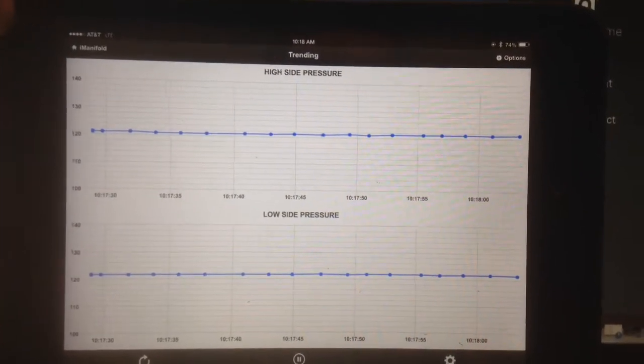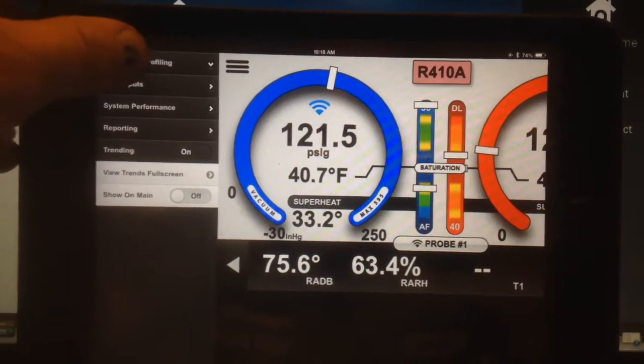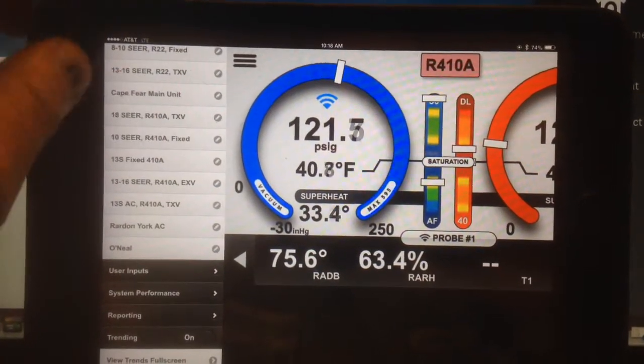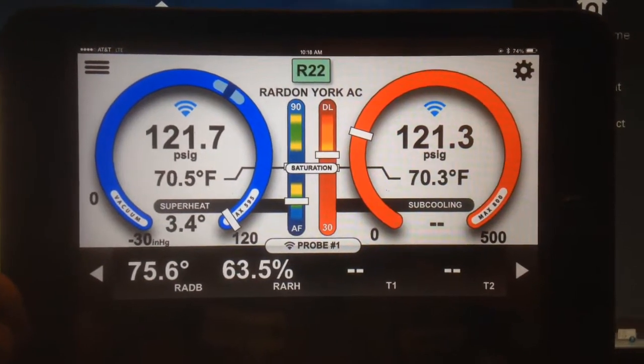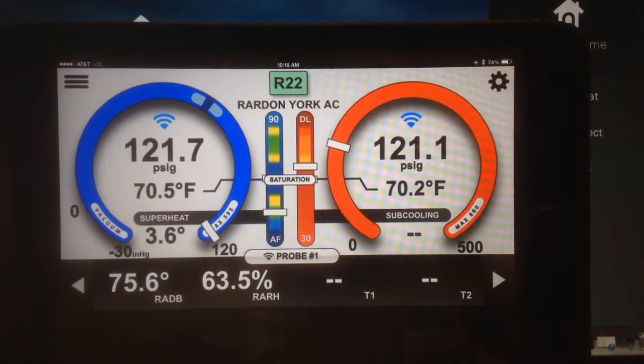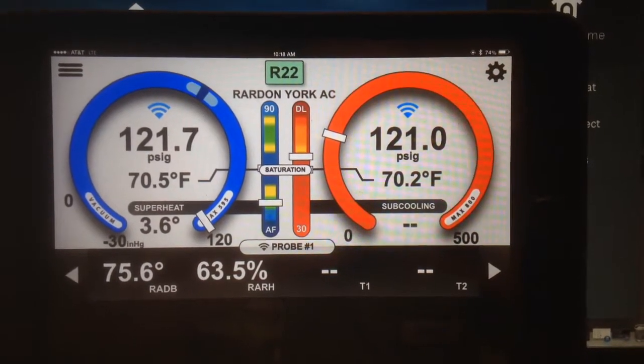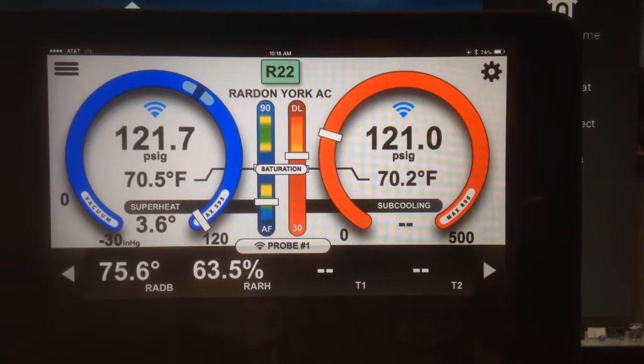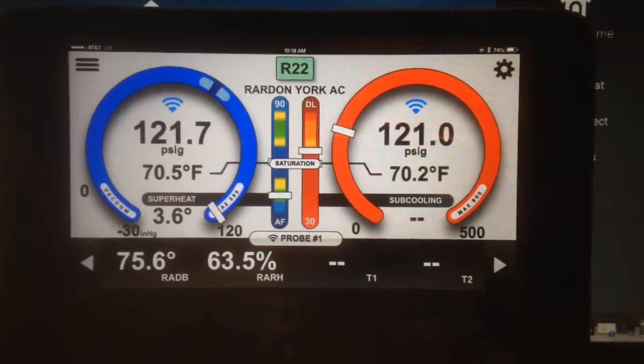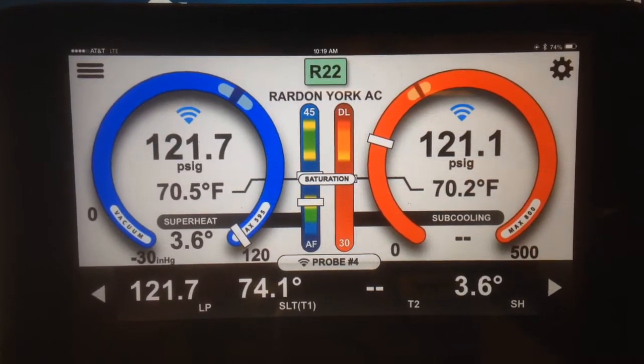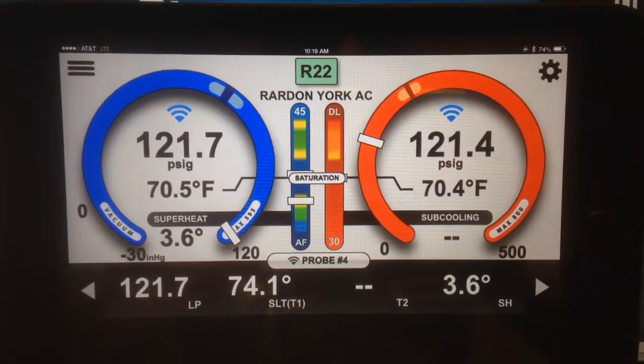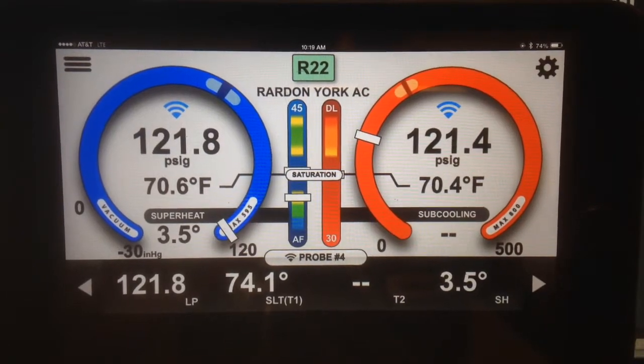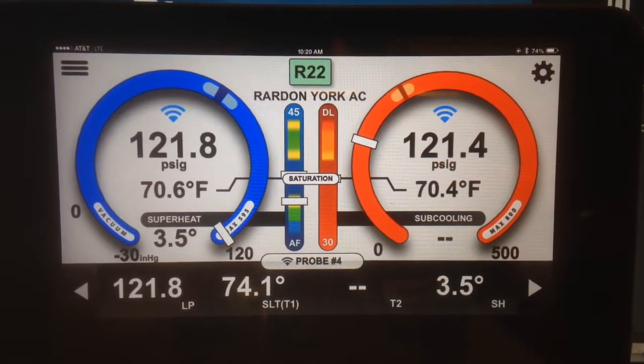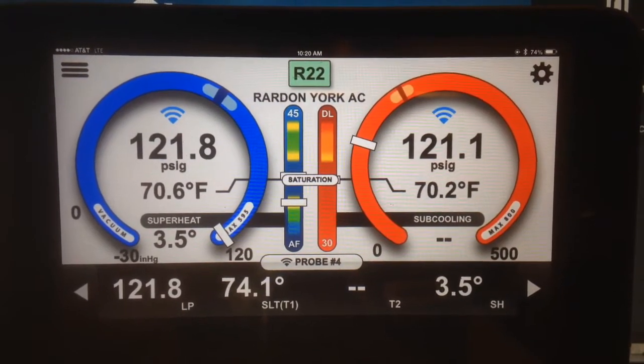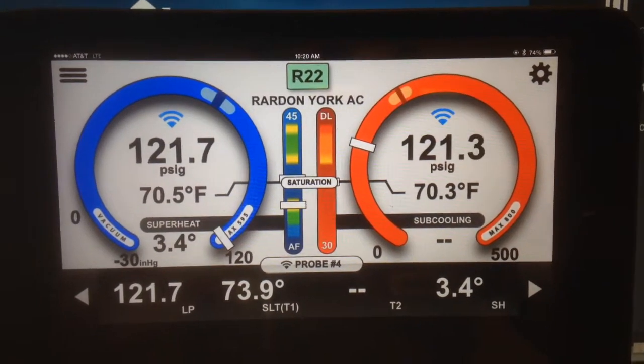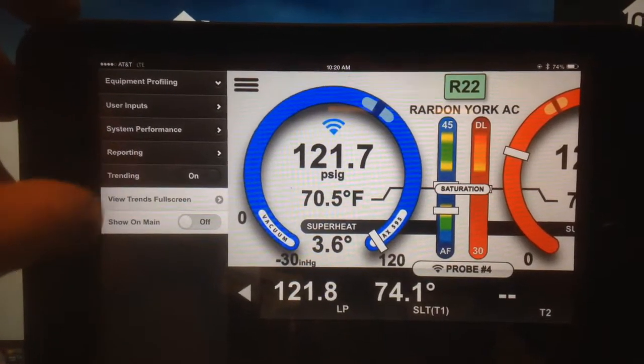We're going to go ahead and go over to the profile, and I have saved my system over here. We've got a piston orifice, and so no target subcooling, and actually I don't have an outdoor ambient. Let me see if I can fix that. So the outdoor ambient is not going to be totally accurate because it is off of the iManifold sitting on my dining room table right now, but at least it'll give us that information based off of ambient in my first floor dining room table.